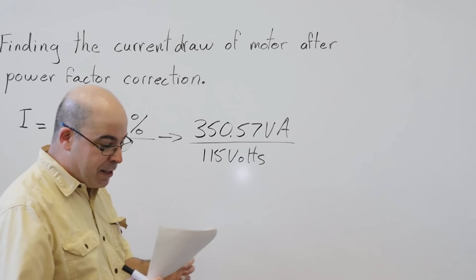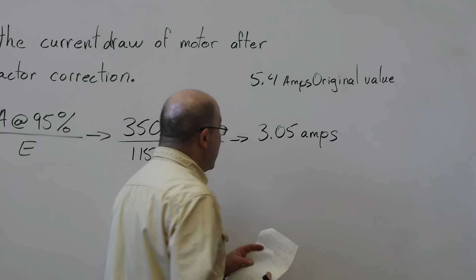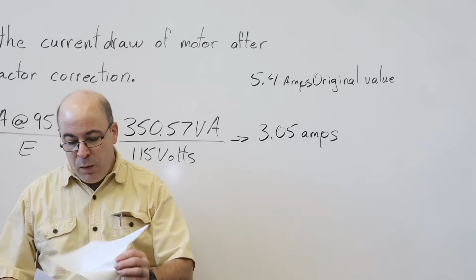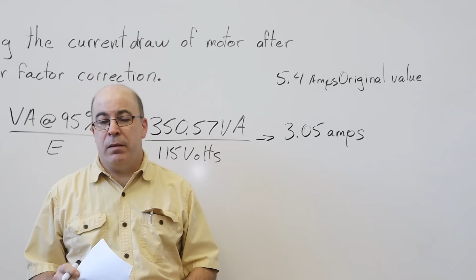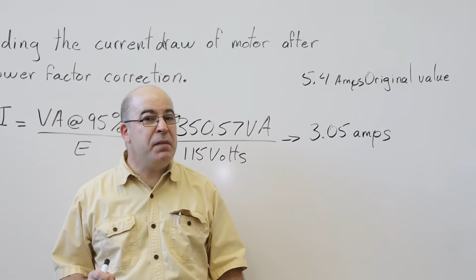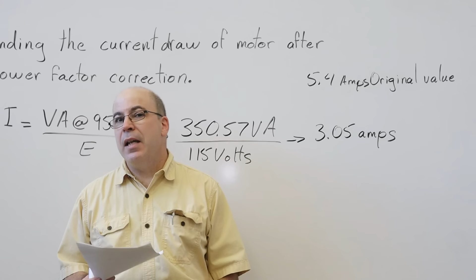amps. So, when we started out, the original value was 5.4 amps. So, in theory, I should have eliminated at least 2 amps of current. So that means I'm going to see a savings over the apparent power, and based on the cost of a capacitor, which typically will run you about $12 to $15, it'll take me less than a year to recover the costs I have spent on doing power factor correction for that one little motor. So now that we've done this, let's take a walk and go back to my garage and see how this is going to work out for us.